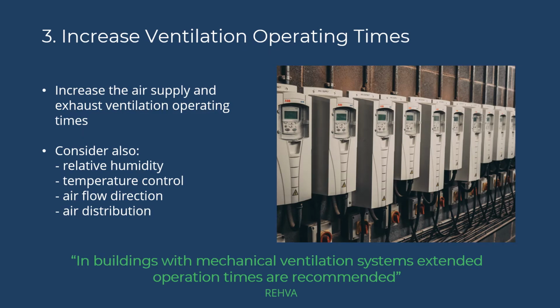The Federation of European Heating, Ventilation and Air Conditioning Associations, REHVA, recommends increasing the air supply and exhaust ventilation operation times in buildings with mechanical ventilation systems. However, HVAC systems are complex and are usually tailored to the specific requirements of individual buildings and production areas. For this reason, extending the operating times is not a matter of simply flicking a switch. Apart from ventilation rate, the other requirements that need to be considered include temperature control, relative humidity, airflow direction, and air distribution. Systems should be customised as needed by HVAC engineers to reduce the risks of airborne transmission.